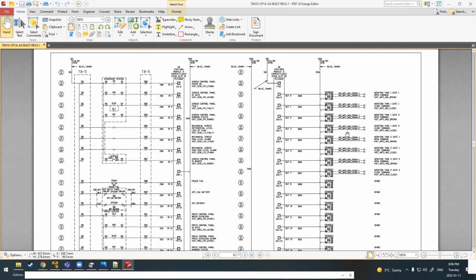For your digital outputs, this particular one is showing it's controlling a relay. So especially for 24 volt relays, there's a lot of field devices that are not 24 volts, they're 120. So you'll have 24 volts comes here, it runs into the card, it'll run through the circuitry inside the card. When the card is told to turn on, in this case, the gate open command, it will then pass power through this relay.